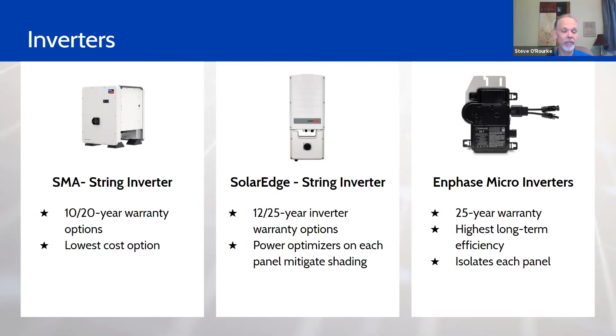The inverter location is a big thing we look for. Typically, if you're doing a ground mount, we're going to mount the inverters right out next to the array to minimize any power losses from the DC components. So the AC will travel from the inverters out of the array into the building. We go and find out where your meter is, where your electrical room is. We generally want to install the equipment where the electrical distribution equipment is. If you have room on the inside of your electric room, that's ideal. When you don't have the inverter out in the elements, the inverters are designed in NEMA certified cabinets, so they're designed to handle weather. But if it's really hot, they're going to be affected somewhat. If it's really cold, it stresses the equipment more. So if they're in a climate controlled condition, it's better.